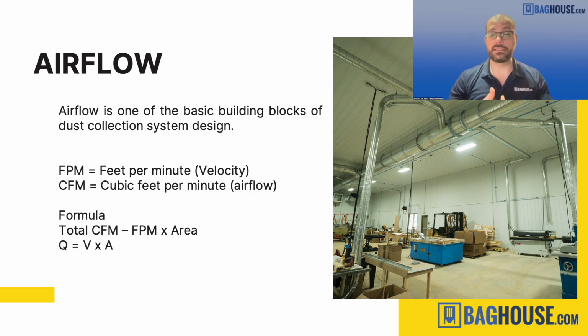If we were to go up to a 6-inch duct at the same velocity of 4,500 feet per minute, then we would have 885 cubic feet per minute. And conversely, if we were to slow down the velocity, say go down to 3,500 feet per minute, in the same 4-inch pipe, now you'd only have 305 CFM as opposed to 395 before. And if you had a 6-inch at 3,500 feet per minute, you'd only have 685 CFM versus 885 CFM at the 4,500 feet per minute.